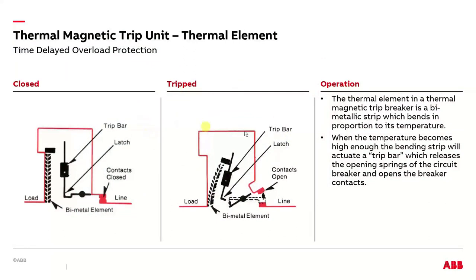So now we get into the thermomagnetic trip unit. Relatively simple. I probably already covered it, but you have a thermal element. And this slide, I'm sorry, is for the thermal element only. So you have your thermal element, which is a bimetallic strip, then your trip bar, which is what opens the contacts for the breaker. And this bimetallic strip, as it gets hotter, will bend in one direction, and then basically trigger the mousetrap and open the breaker. The thermal response is kind of an I squared T response, with a little bit of a curve to it.